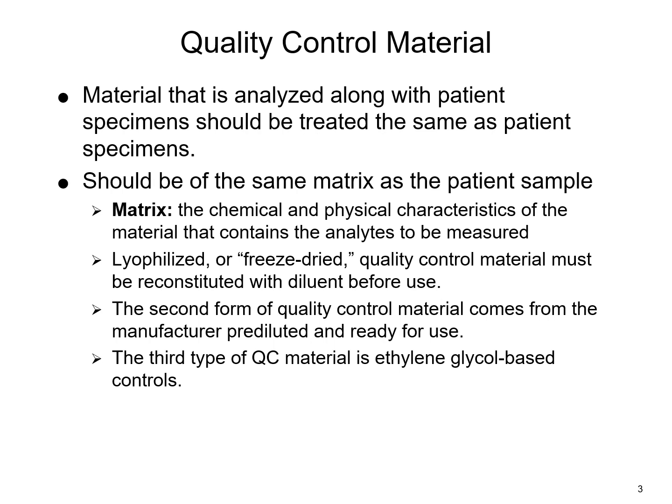That material needs to mimic what serum is. Likewise, if we're measuring something in the urine, then we need to make sure that that material has the same consistency and characteristics as a urine sample. So the manufacturers will develop a quality control material that will match whatever you're testing.